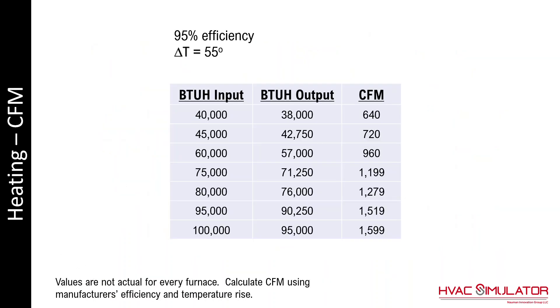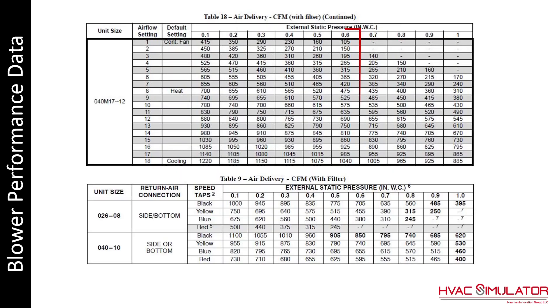This chart represents multiple BTU inputs of furnaces with the calculated CFM. These values may not be correct for every furnace — calculate CFM using the manufacturer's efficiency and their temperature rise. On the top chart, there are 18 blower speeds with approximately 900 CFM between the lowest and highest speeds. On the bottom chart, there's only 255 CFM from the lowest to the highest speed, making it critical to set up these speeds correctly to ensure the furnace is running at peak performance.